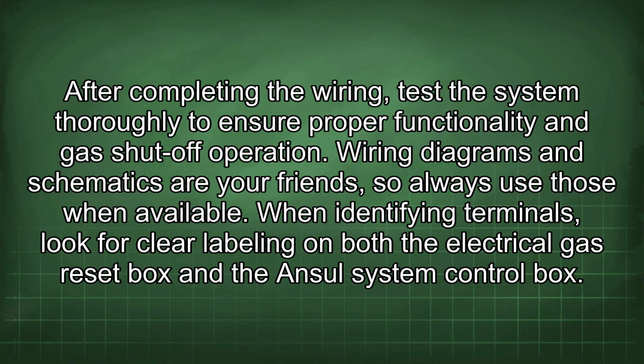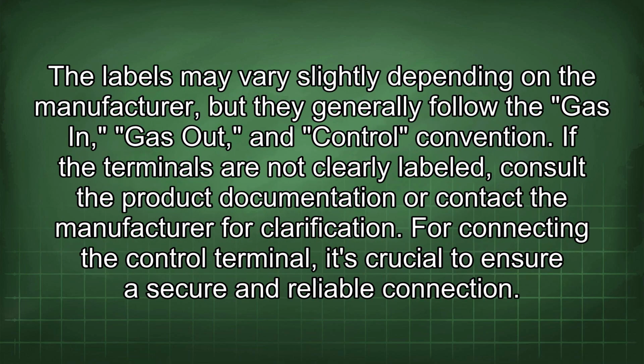Wiring diagrams and schematics are your friends, so always use those when available. When identifying terminals, look for clear labeling on both the electrical gas reset box and the Ansul system control box. The labels may vary slightly depending on the manufacturer, but they generally follow the gas in, gas out, and control convention. If the terminals are not clearly labeled, consult the product documentation or contact the manufacturer for clarification.